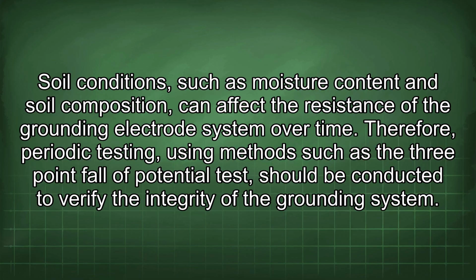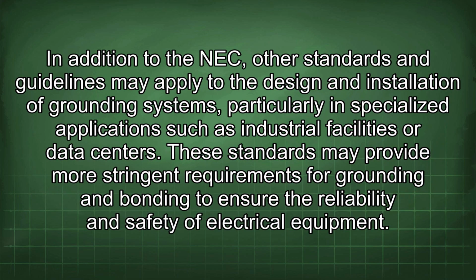Therefore, periodic testing using methods such as the 3-point fall of potential test should be conducted to verify the integrity of the grounding system. In addition to the NEC, other standards and guidelines may apply to the design and installation of grounding systems, particularly in specialized applications such as industrial facilities or data centers. These standards may provide more stringent requirements for grounding and bonding to ensure the reliability and safety of electrical equipment.